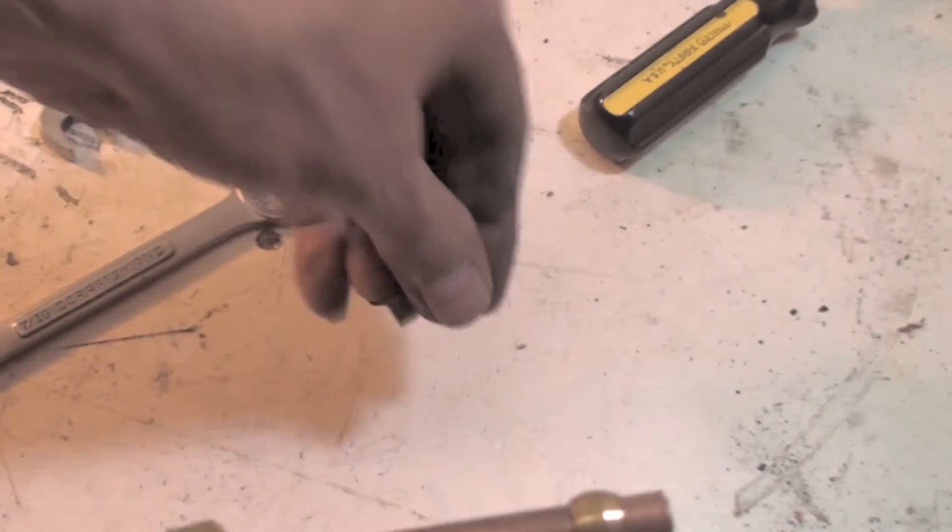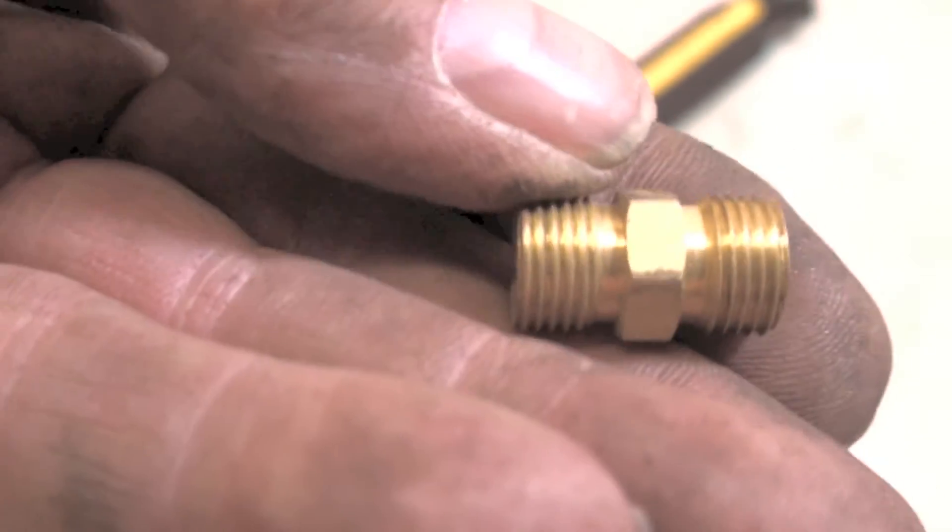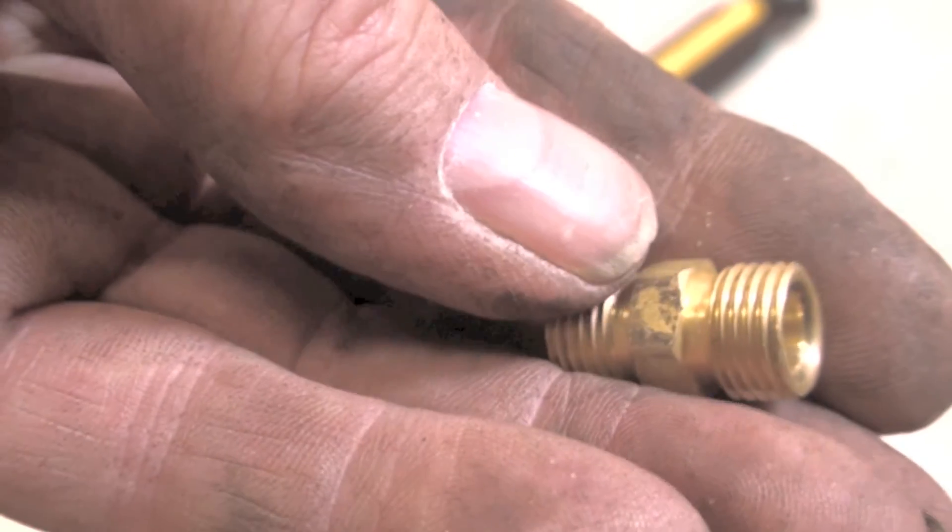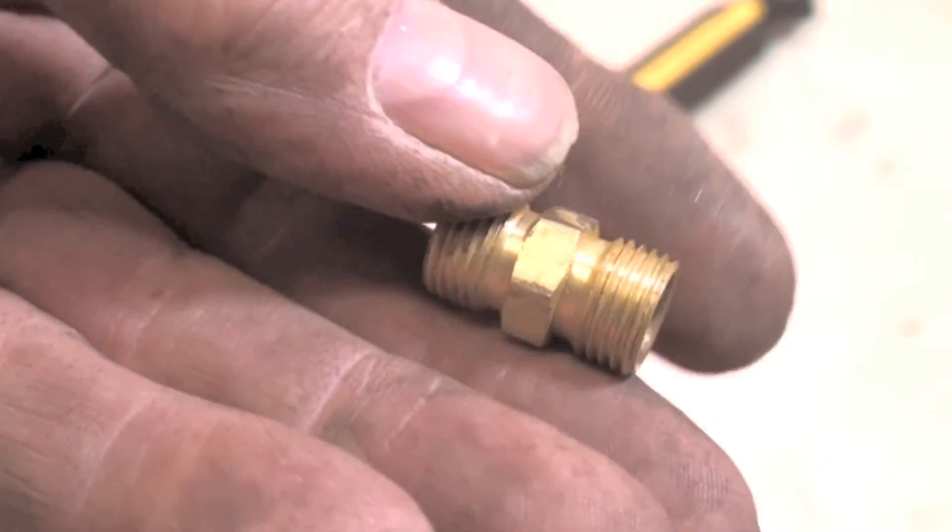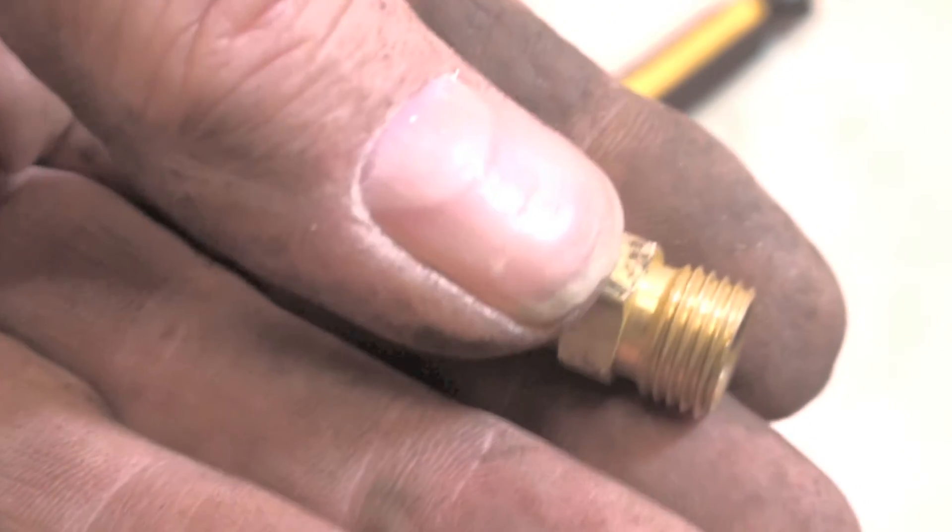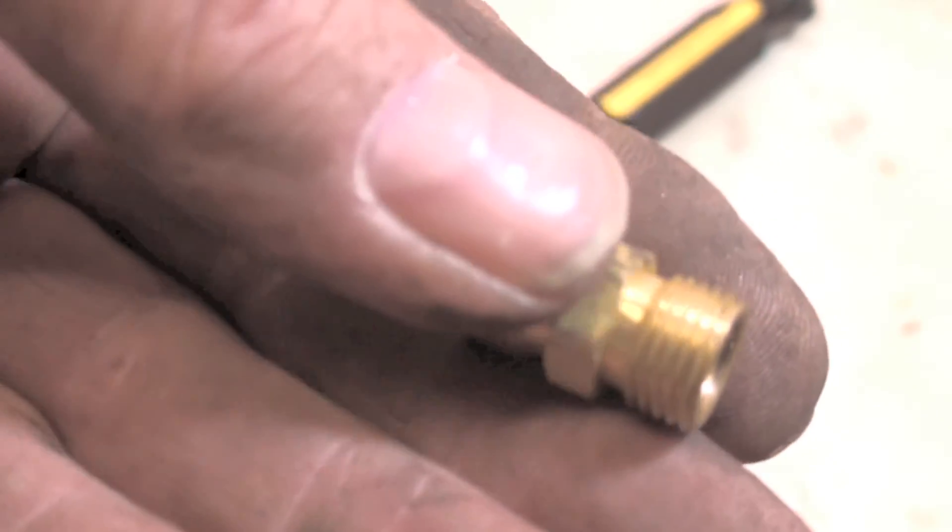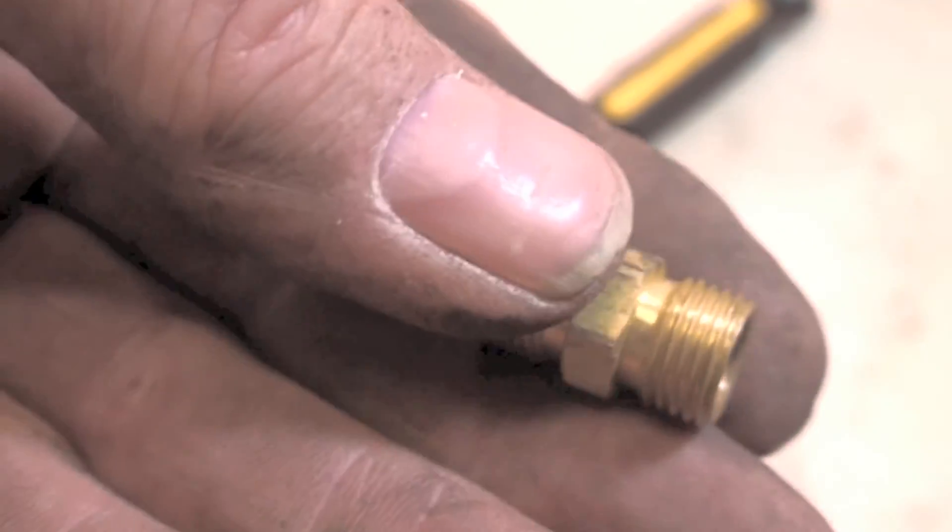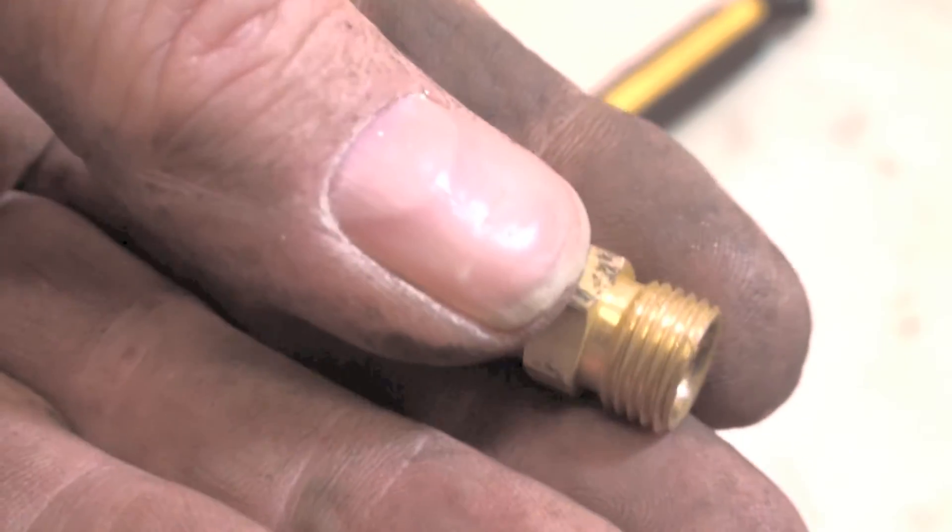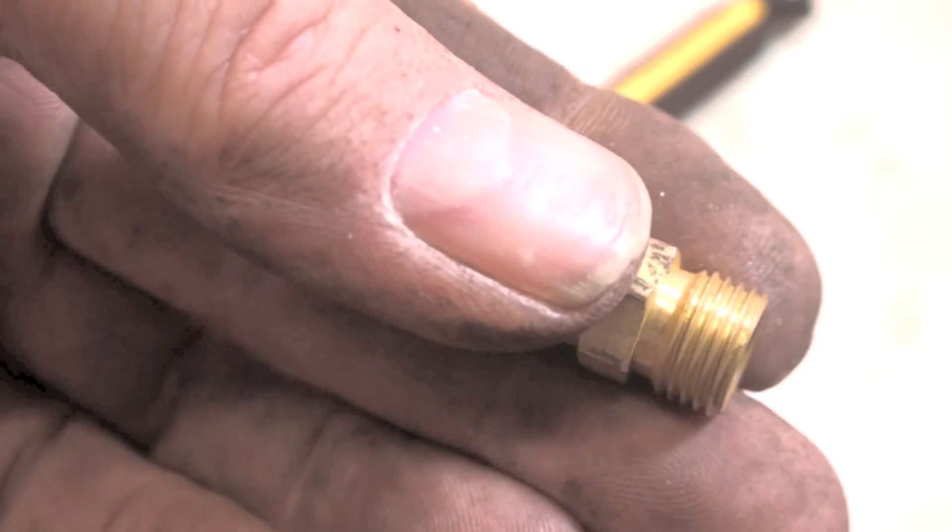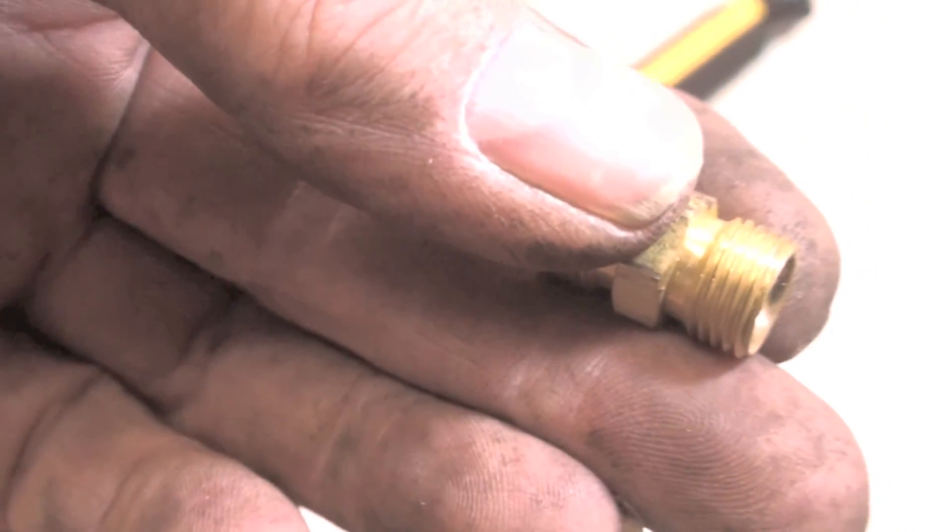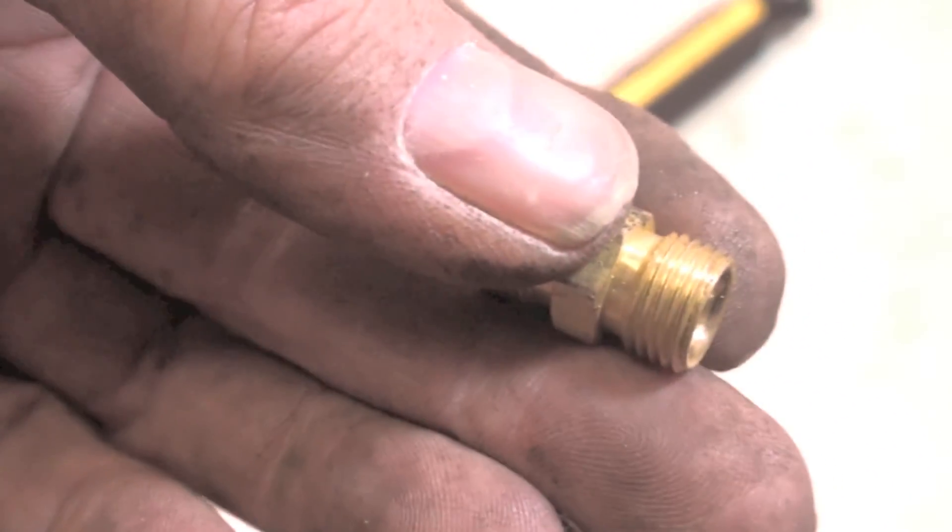If you want to, you can put some pipe dope on the threads. The reason you're putting pipe dope on the threads is not to seal it—because pipe dope is a sealer but it's only for tapered threads—but it's a lubricant. You can use oil too. If you tighten down with some sort of lubricant on the threads, the pressure you're putting on there with your wrenches will be transferred to the fitting rather than being eaten up on the threads.